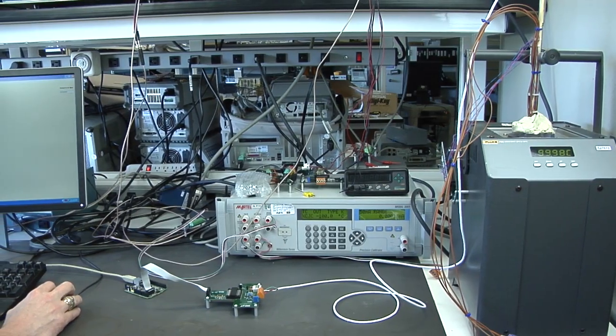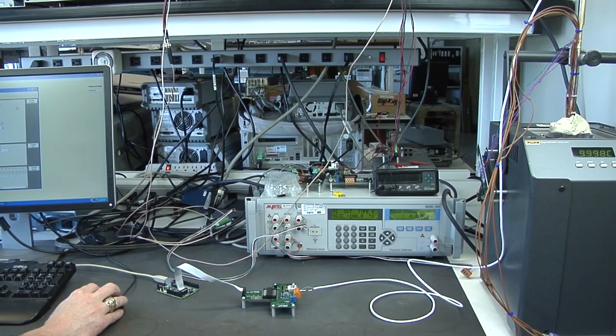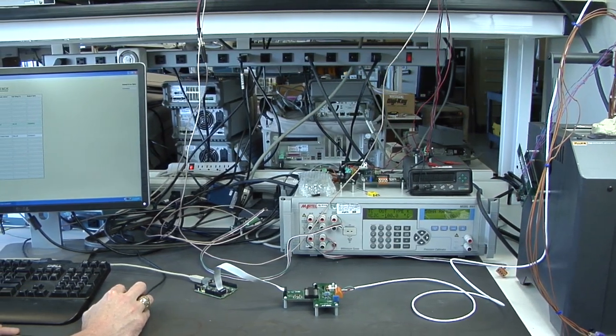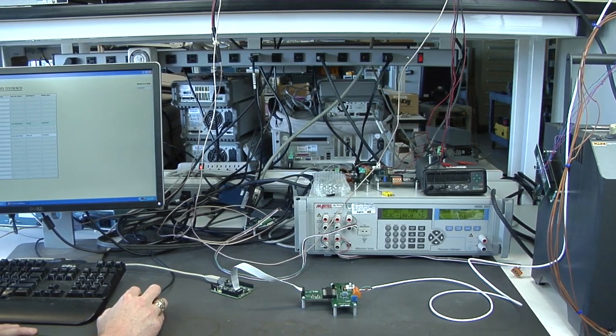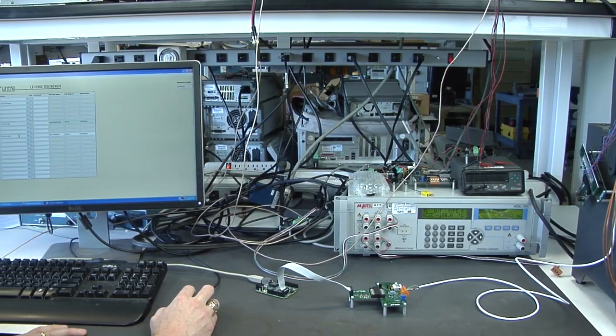One such sensor is the RTD. An RTD is a device that changes resistance as a function of temperature. RTDs can be configured as 2, 3, or 4 wire connections and have several standards, i.e. temperature coefficients, as well as nominal resistance values at 0 degrees C.